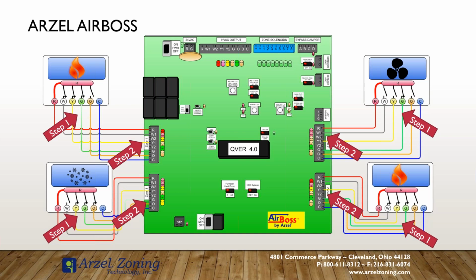So if your thermostat is calling for heat, and the other thermostat's calling for cooling, you can set a priority between heating and cooling calls and it will serve that priority. With the Heat Pump Pro, and we would talk about it more in depth with the Setup Wizard, you have heating priority, cooling priority, zone weight priority, or auto. With the AirBoss, you have auto, heating, or cooling because there's no zone weight. But automatic is first come, first serve.